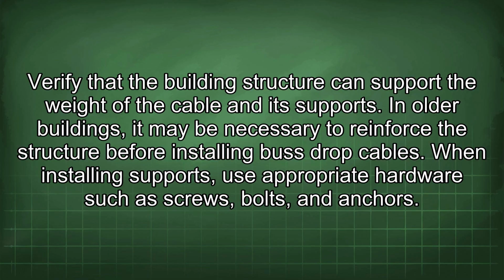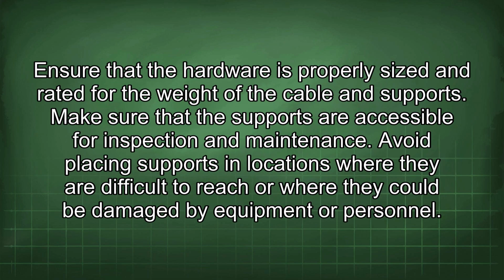When installing supports, use appropriate hardware such as screws, bolts, and anchors. Ensure that the hardware is properly sized and rated for the weight of the cable and supports. Make sure that the supports are accessible for inspection and maintenance. Avoid placing supports in locations where they are difficult to reach or where they could be damaged by equipment or personnel.